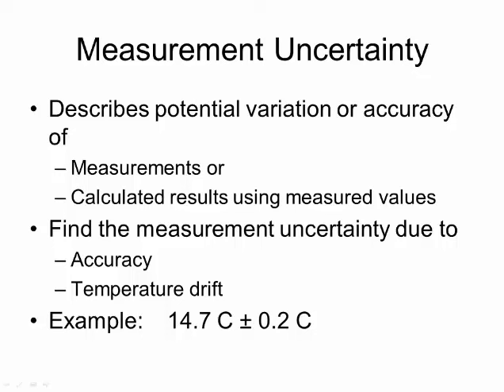For example, if you had a temperature measurement system with an uncertainty of plus-minus 0.2 degrees Celsius, and the reading you obtained was 14.7 degrees Celsius, the correct way to write it is 14.7 degrees Celsius plus-minus 0.2 degrees Celsius. This communicates to the reader that your measurement system could not distinguish temperatures from 14.5 to 14.9 degrees Celsius.